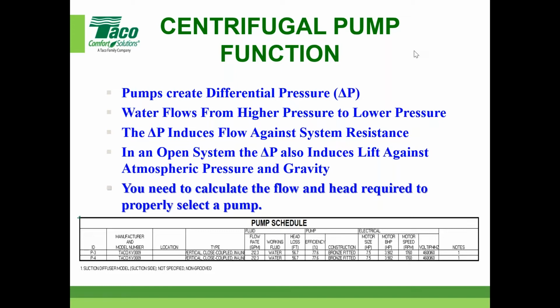That delta P induces flow against system resistance. So us engineers get involved with this quite a bit—you have to do system resistance calculations to help size the pump. The head loss, the differential, all of that terminology you have to get involved with. That's very, very important.